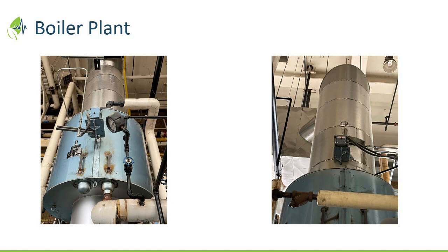Like that photo on the right side is the draft damper above the economizer that was installed at the time. The same thing, it's way up there. It's almost impossible to know, like there's no instrumentation on a lot of these older plants to understand what the position of that actuator is. So, you know, even if you put these measures in place, you might need the draft in the summer just to maintain on the boilers, right? Especially as you really tighten up combustion, you still need a slight negative at all times. So I don't think you can cut down stack measures. You just have to control them.